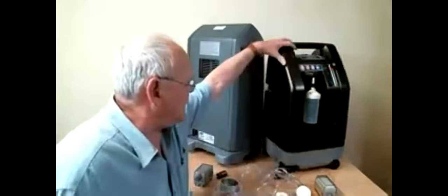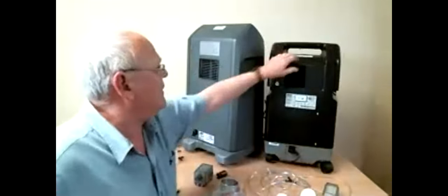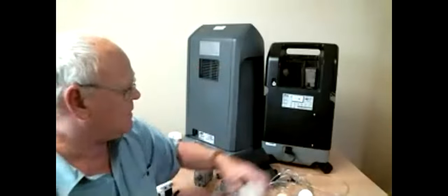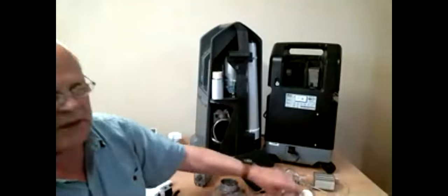If we look at the other one here, this has a gross particle filter on the back, but it's under a cover. We can take that cover off to see the filter. And this one has a secondary filter inside here. Looks like this. They simply pull out and you can replace them. With this one, a secondary filter is inside. You can take the cover off, and that just sits on top here. And so just a simple felt filter.